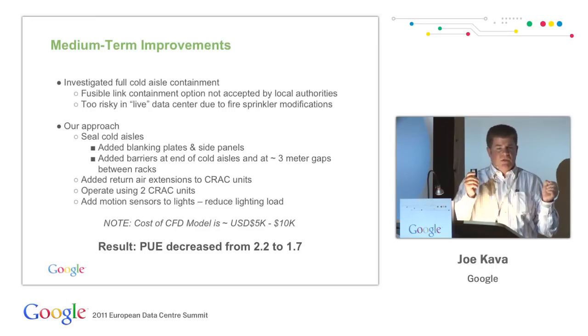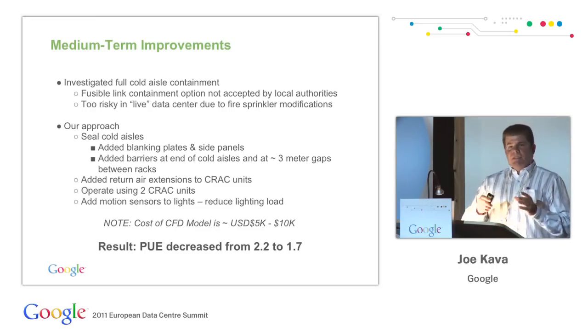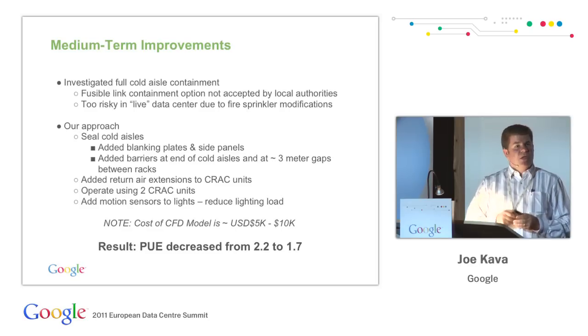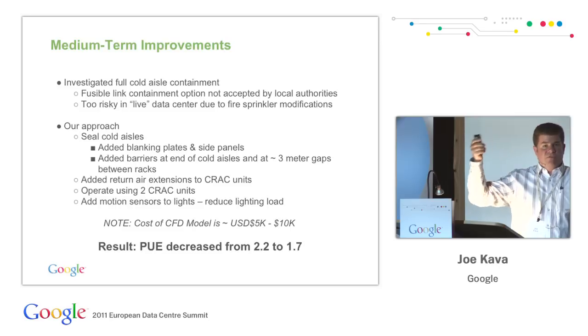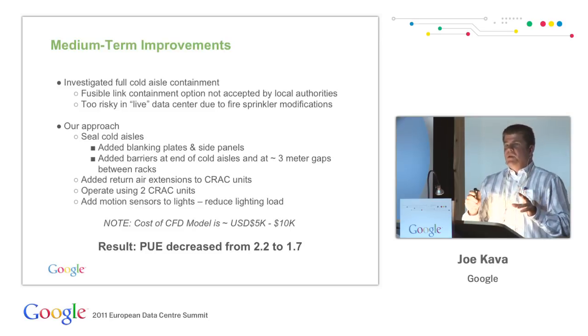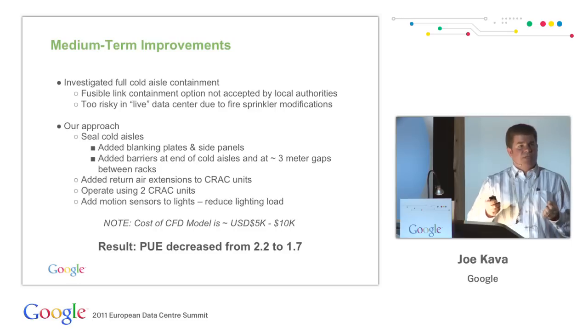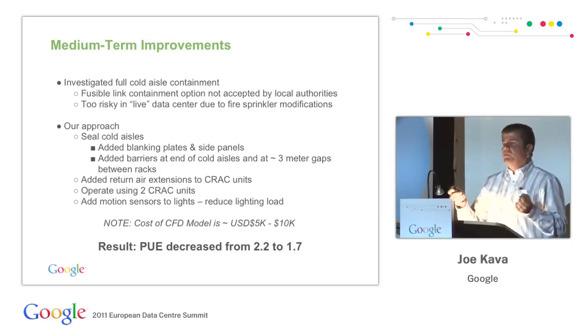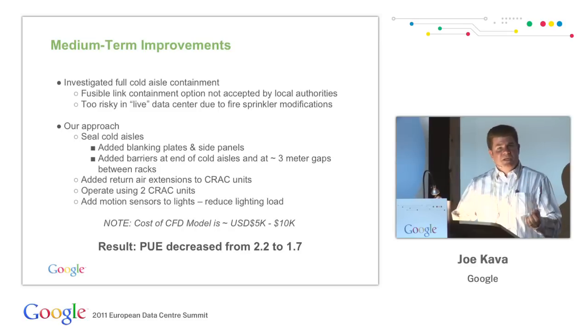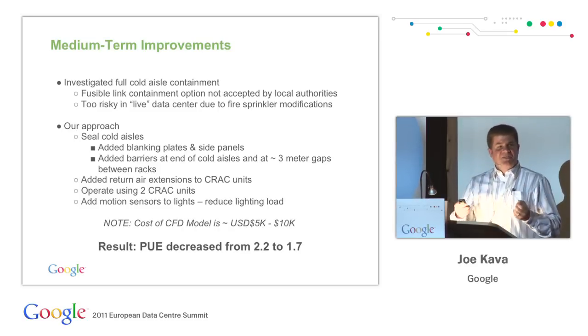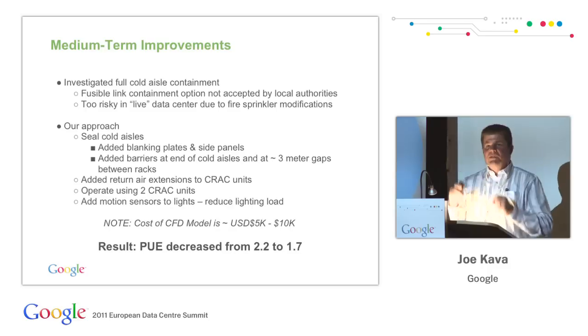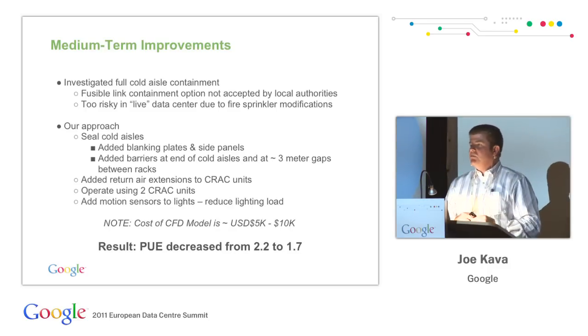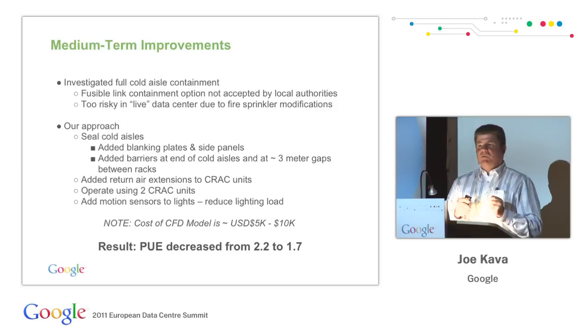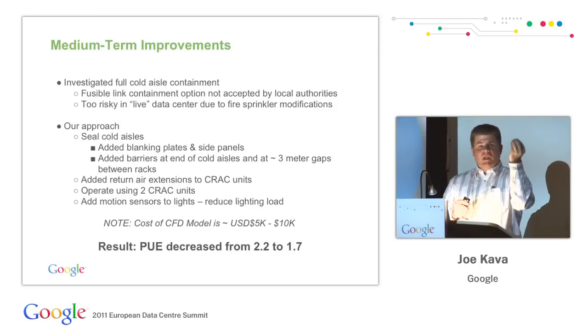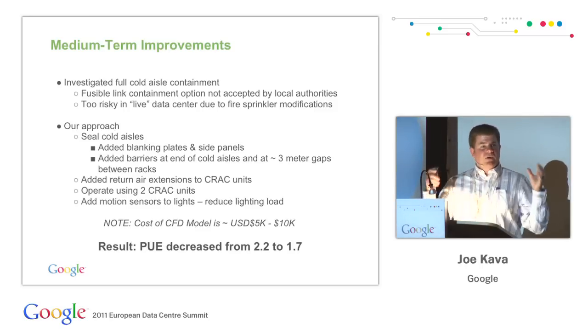We first focused on good cold aisle containment. We investigated a full containment solution. There's many commercial products available now that have lids over the cold aisle. They're fusible link lids. But the problem that we encountered is that we were doing these upgrades in various different geographies where there were multiple authorities having jurisdiction, and they had opinions about this. And some of those opinions were that you can only do that if you modify the current sprinkler system. And in one specific case, the authority wanted us to drop the sprinkler system down low enough so that it was within the cold aisle containment.